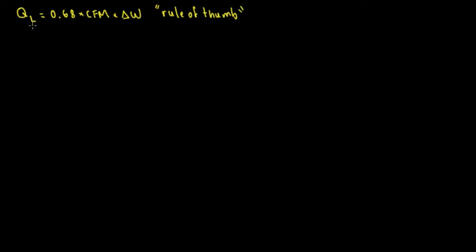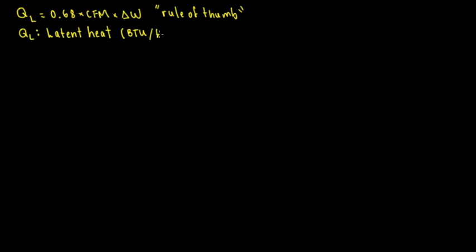In this equation, QL is going to be the latent heat. It's not talking about a specific latent heat — this is going to be the total latent heat, which takes into account the moist part in air. Because we have dry air and wet air, this is the wet portion. The units are going to be BTUs per hour. Since we're talking about time, a proper way to express this would be with a dot, which indicates a rate — BTUs divided by time.